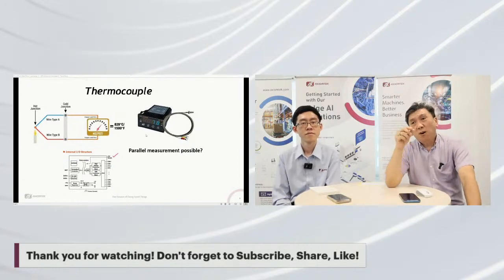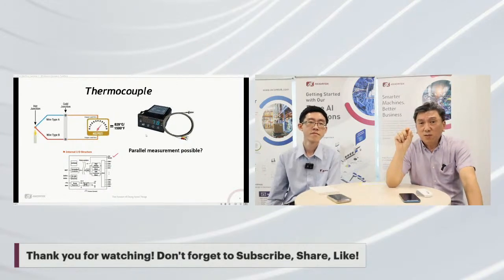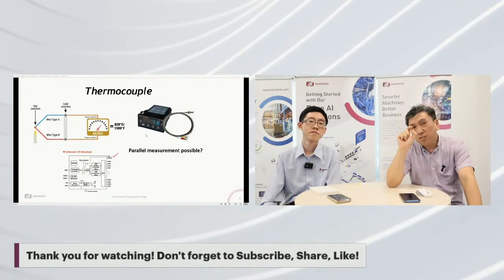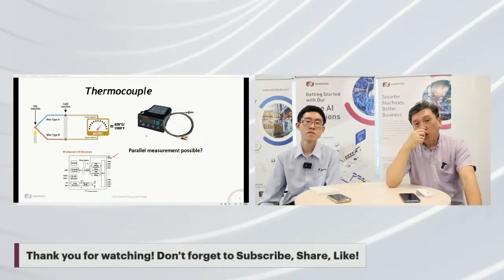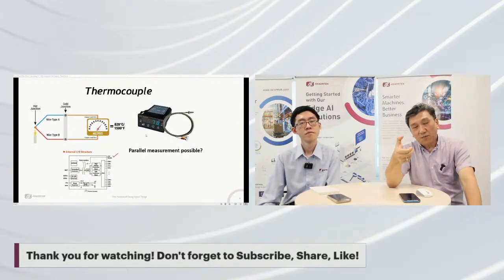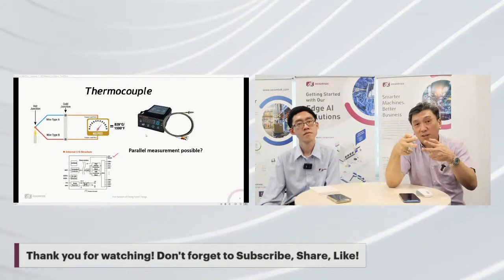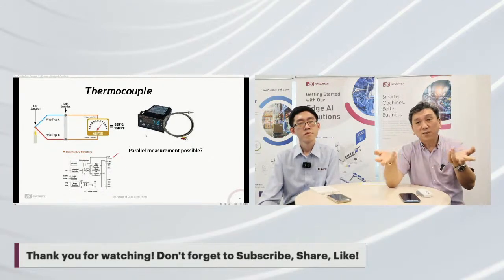There's something called open channel detection in thermocouples. When you have this open channel detection, you are not able to parallel this together. So you have to use the right equipment. For example, we have one of the modules that is able to tap directly into it, and then we can do it.